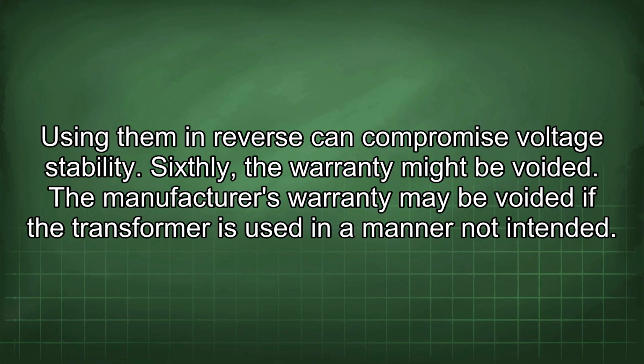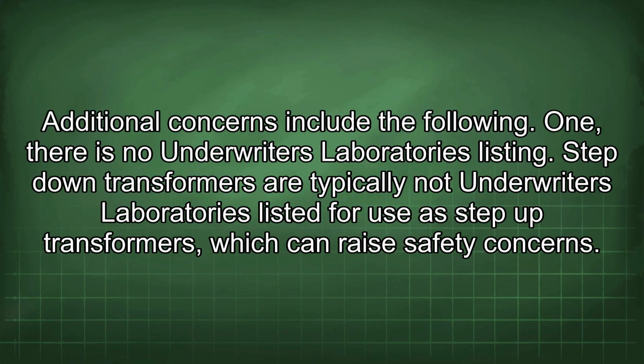Sixthly, the warranty might be voided. The manufacturer's warranty may be voided if the transformer is used in a manner not intended. Additional concerns include the following. 1. There is no Underwriters Laboratories listing. Step-down transformers are typically not Underwriters Laboratories listed for use as step-up transformers, which can raise safety concerns.